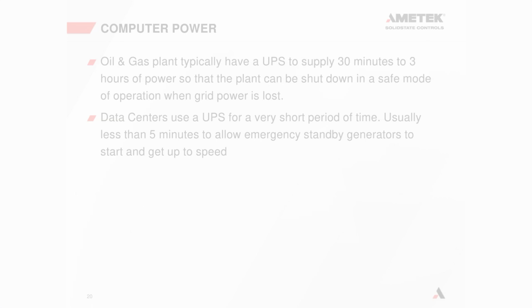For oil and gas plants, they'll typically have a UPS that supplies from 30 minutes up to 3 hours of power. That's basically so that the plant can be shut down to a safe mode of operation when the grid power is lost. They can put the valves in position, vent any gas out to the flare stack, and release pressure in vessels, everything they need to do to get the plant to a safe mode when the grid power is lost. That is what the UPS is there for.